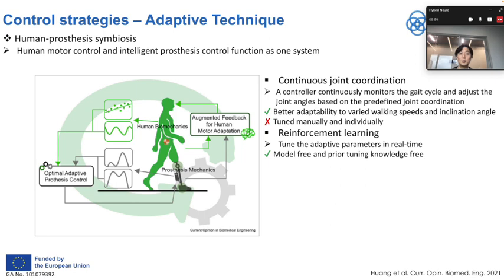This example is more common in lower-limb prostheses: using an adaptive technique is another way to increase intuitiveness. The idea is to have the system with human motor control and intelligent prosthesis control functioning as one system. The controller continuously monitors the gait cycle and adjusts joint angles based on predefined joint coordination. Although this can adapt to walking speed and inclination angle, manual tuning is needed — and to overcome this burden, reinforcement learning has been proposed and proven to be effective.